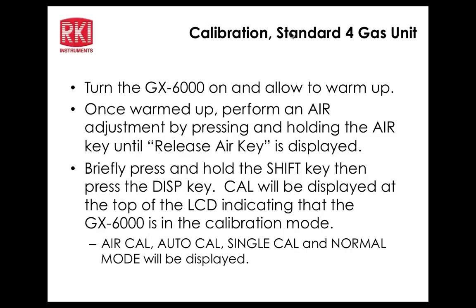Okay, now it's calibrated to 100. Okay, now we are done. Disconnect the gas. We're back to the sub menu of the calibration menu. And I just want to simply go to escape now. Now, ordinarily, if you don't want to hear the alarms, just go ahead and let it run like this with the alarms deactivated. But if you go quickly to escape, you'll probably get some alarms, likely.